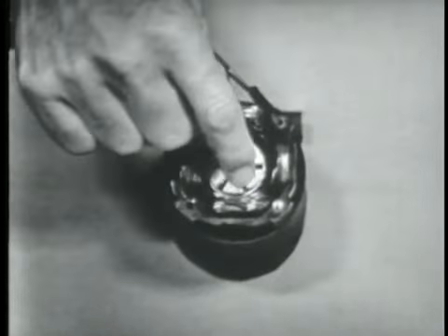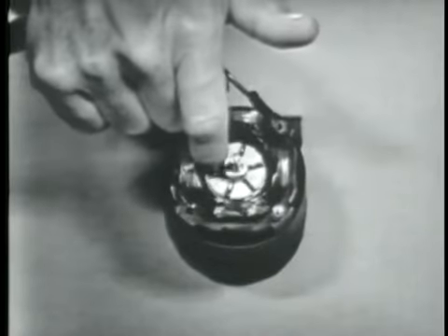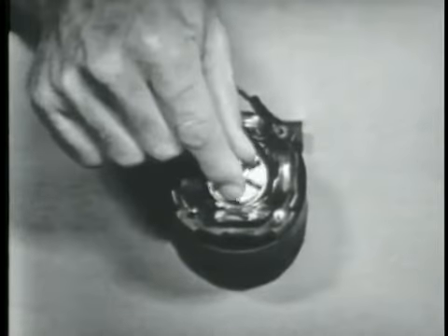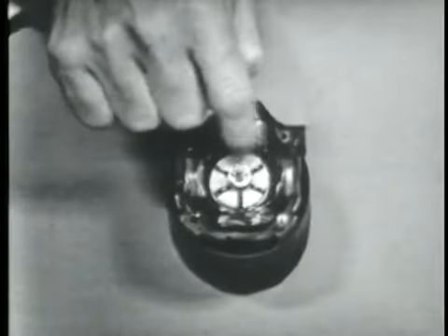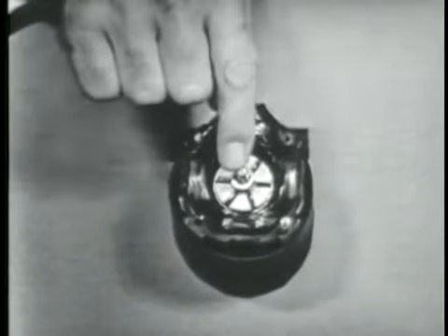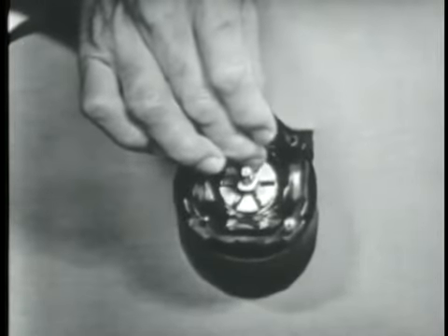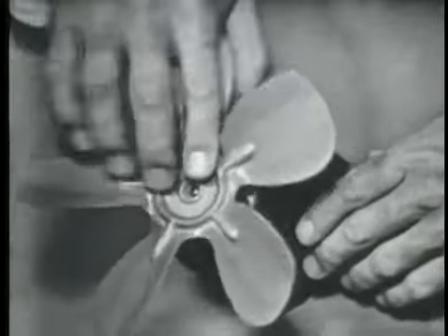Right. The same thing is true of this rotor. That is, it takes a certain amount of energy to overcome its weight to cause this hunk of iron to turn. And, of course, the friction of the rotor shaft on the bearings adds to the internal load. And there's a little cooling fan built into the rotor, and that increases the internal load. Now, the external load refers to the job or the work that the rotor must do. That is, turn gears or operate pulleys, or maybe turn a fan blade.